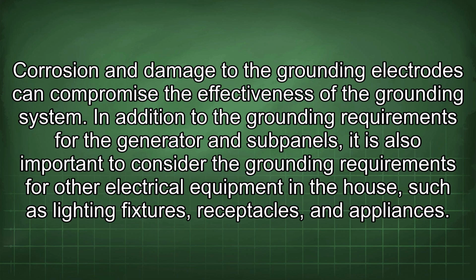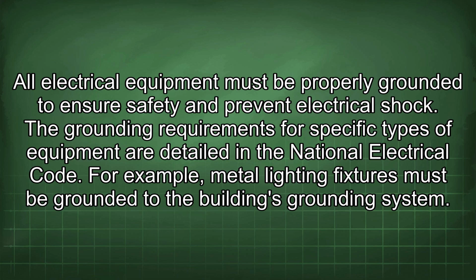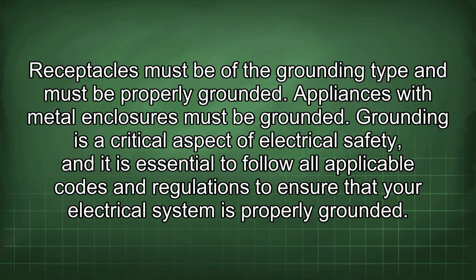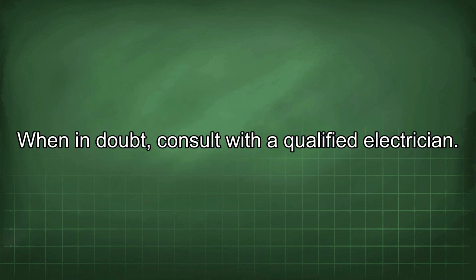In addition to the grounding requirements for the generator and subpanels, it is also important to consider the grounding requirements for other electrical equipment in the house, such as lighting fixtures, receptacles, and appliances. All electrical equipment must be properly grounded to ensure safety and prevent electrical shock. The grounding requirements for specific types of equipment are detailed in the National Electrical Code. For example, metal lighting fixtures must be grounded to the building's grounding system. Receptacles must be of the grounding type and must be properly grounded. Appliances with metal enclosures must be grounded. Grounding is a critical aspect of electrical safety, and it is essential to follow all applicable codes and regulations to ensure that your electrical system is properly grounded. When in doubt, consult with a qualified electrician.